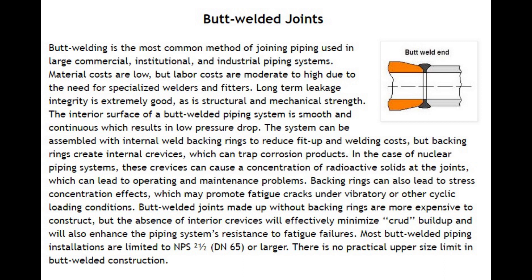Backing rings can also lead to stress concentration effects, which may promote fatigue cracks under vibratory or other cyclic loading conditions. Butt welded joints made up without backing rings are more expensive to construct, but the absence of interior crevices will effectively minimize crud buildup and will also enhance the piping system's resistance to fatigue failures.